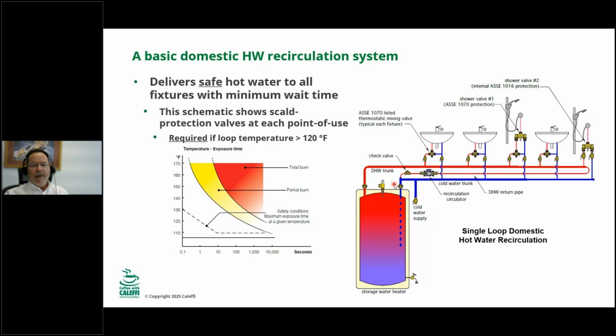Now, if we were running this tank at 120 and sending out 120 degree water through the building, which would be more like a residential application, we wouldn't need those anti-scald valves. But now we're getting into some temperatures that are more than 120, and that can be problematic. I'll show you why.